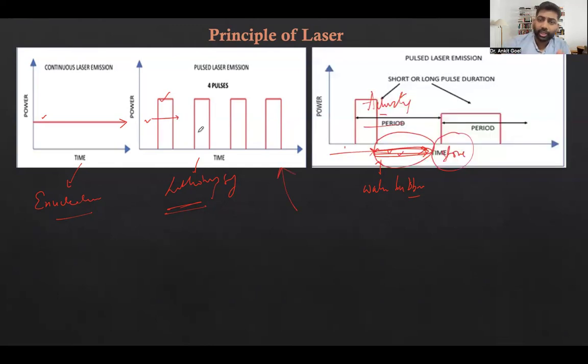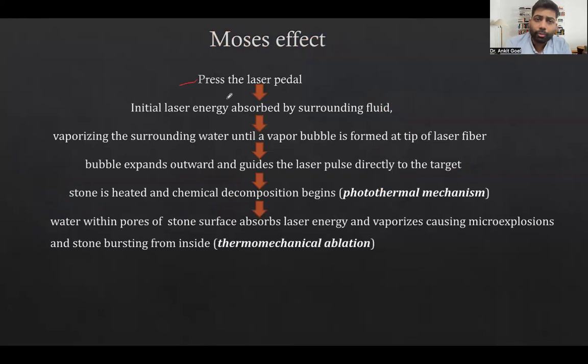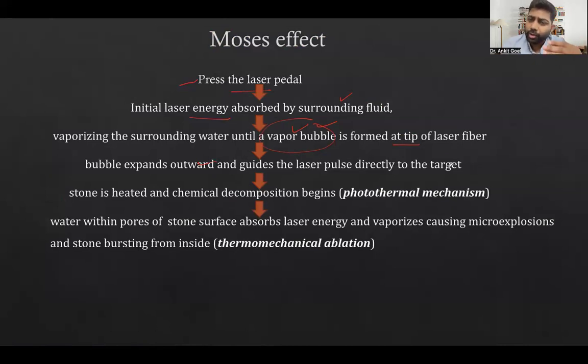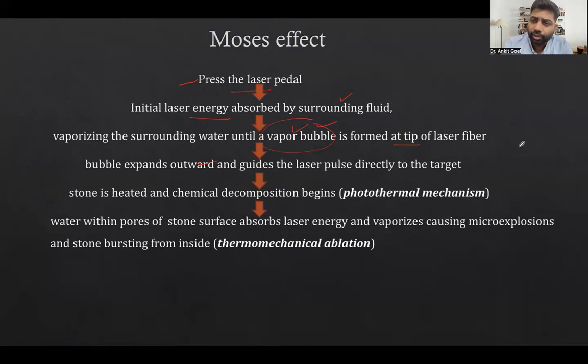To summarize: when you press the laser pedal, the initial energy is absorbed by the surrounding fluid and forms a vapor bubble around the tip of the laser. This bubble expands and moves toward the target, but with some dissipation of energy. The energy that is ultimately transmitted to the stone is what causes the lithotripsy.